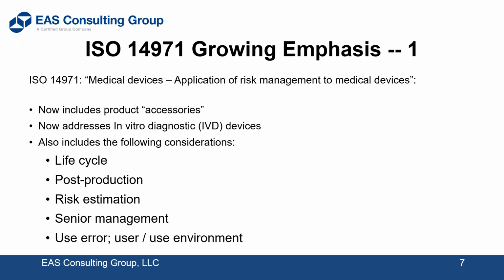Obviously, senior management should be involved in all of this, as well as full support of your quality management system. And use error has always been a no-no. To me, and the FDA as well, it tends to be a default complaint resolution, which is not a resolution. The FDA feels that you need to reduce risk as low as possible. You need to reduce use error, mistake-proof products, use usability engineering, IEC 62366-1, human factors engineering. The FDA started emphasizing that in the year 2000, and now, of course, we have the update to IEC 62366-1 on usability engineering to push away the use error factor.